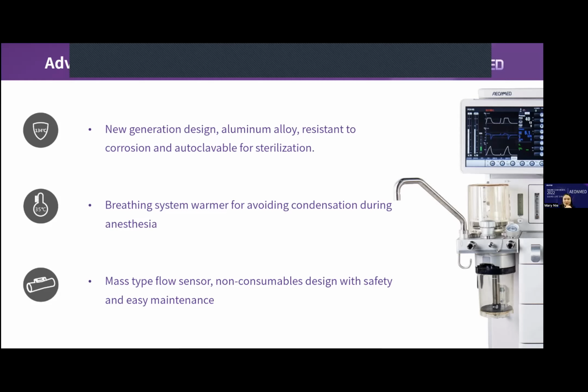And also the flow sensor here, we made it integrated. It's a built-in one, so we don't have to change it every half year or once a year. And we don't have to worry about damage, or somebody from other departments, an intern, just coming into my OR and throwing it away, and I lose my flow sensor. No, we don't have to worry about it. And then we have the unique patterns in these two, and that's why we're confident enough to put it in.